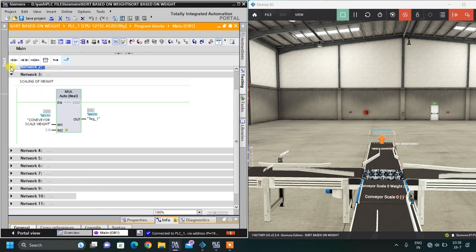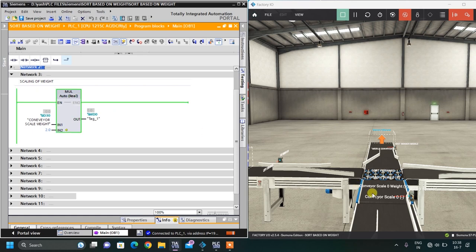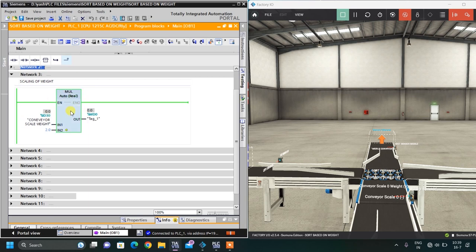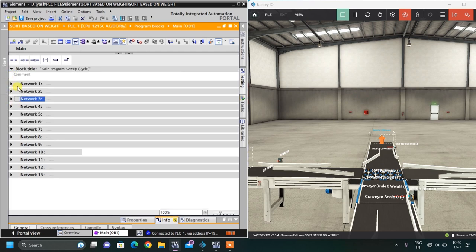The third network is for scaling the analog input. The scale gives 0 to 10 volts, and my configuration is 20 kg maximum, so for 10 V = 20 kg, meaning 1 V = 2 kg. Whatever value I get at ID 30, I multiply it by 2 to get the weight in kg. I used a multiplier block, set data type to real, with ID 30 as input 1, 2.0 as input 2, and the result stored at MD 0 — which is my current box weight.